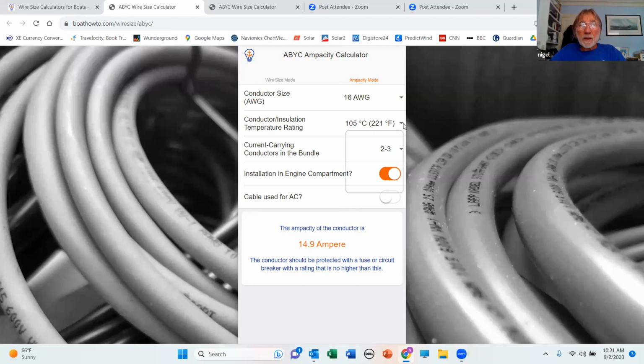So the reason for going to the 90-degree column, even with 105-degree conductors, is partly to be conservative, but partly because most of the devices in that circuit, the fuses, the switches, and so on, are tested at 90 degrees, not 105. And when they get close to 90, they're relying on the conductor to take heat out of the device. During testing, they're connected up to conductors that are helping to keep the temperature down. So if you stick a 105-degree conductor on there and run it at 105 degrees, instead of absorbing heat from the fuses and so on, you're actually going to add heat to the system. In the case of fuses, because they're thermal devices, you're likely to get nuisance blowing of the fuses. You can also get meltdown boots on fuses and have all kinds of other problems.